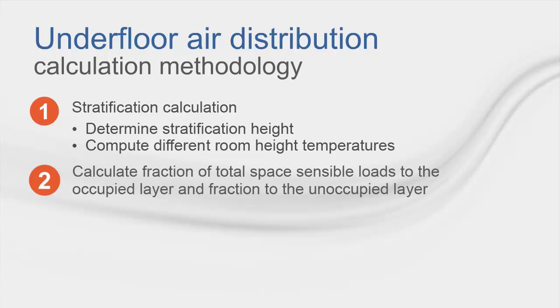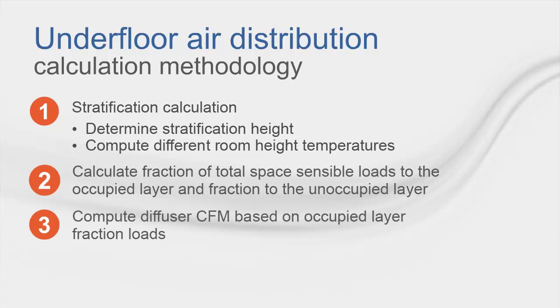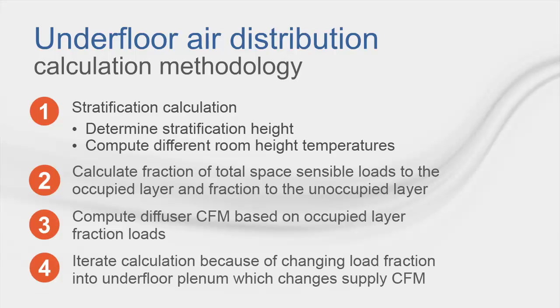Next, based on the stratification calculation, an average occupied zone temperature is used to calculate the fraction of total space sensible loads. This fraction of total space sensible load is used to calculate the load to the upper stratified layer, which in turn will calculate and determine our return air conditions. Then, trace will determine the diffuser CFM based on occupied layer fraction loads. And finally, the iteration of this calculation has to occur because of the constantly changing loads, which in turn we need to reach steady state for our analysis.